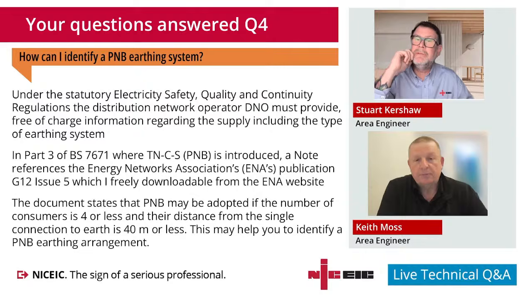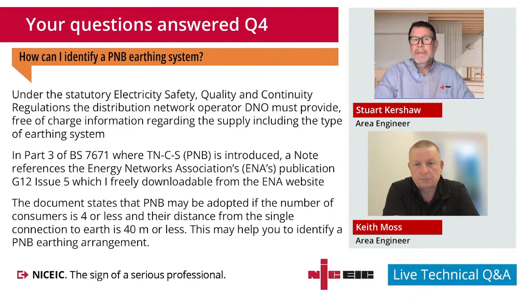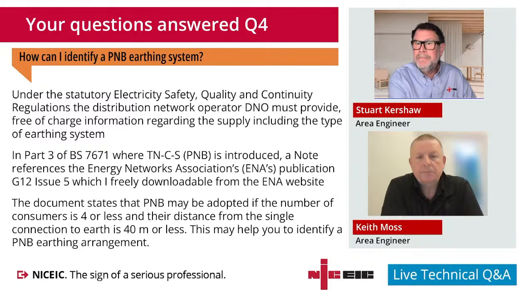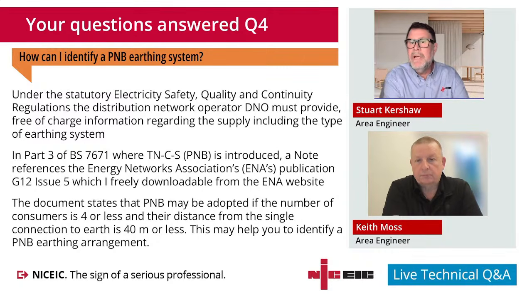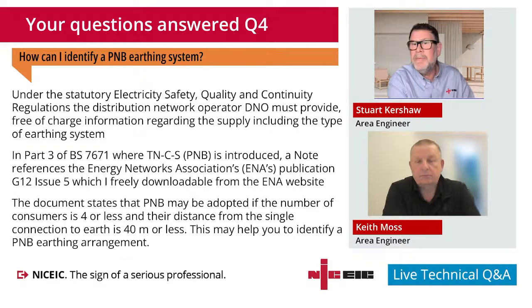Yeah, spot on, and that's actually come through in one of the questions tonight, which is also spot on, because there's a statement, isn't there, that if you are doing that in a prosumer installation that allows you to go into island mode, you're not allowed to rely on the DNO earthing arrangement anymore. That's in the code of practice for electrical energy storage systems, isn't it? The requirement for if you've got a grid connected or grid tied type gateway and a battery, that you must install a supplementary electrode for that.